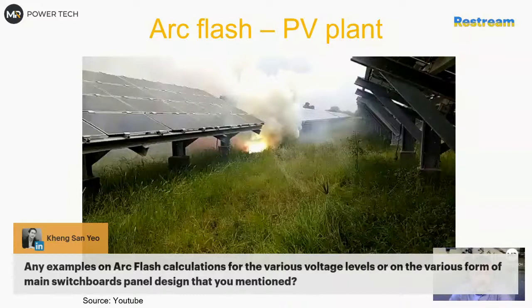Usually the bigger problem is on the low voltage systems, where you actually go to bigger short circuit currents, and sometimes surprisingly high tripping times. That depends on the configuration. The worst thing that you can have is, for example, the main breaker with an ACB configuration, which is horizontally directed into you, creating a kind of ejected arc towards your face or your torso. This is generally considered the general worst case.